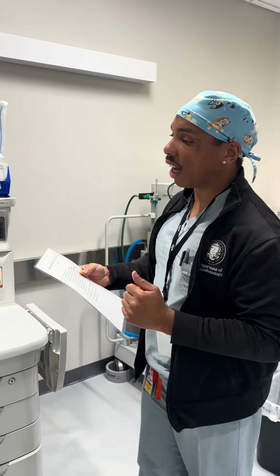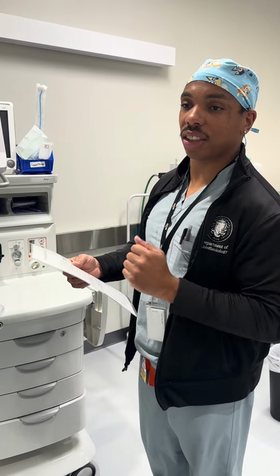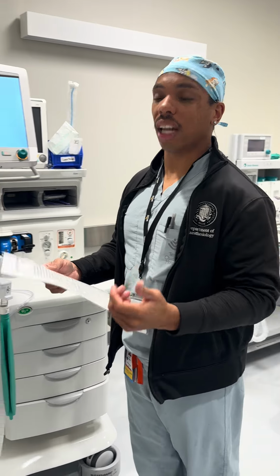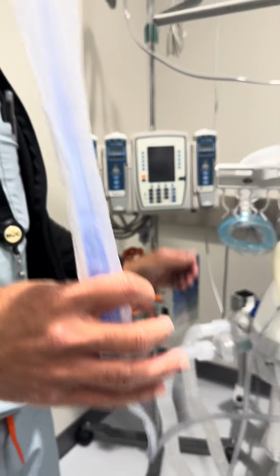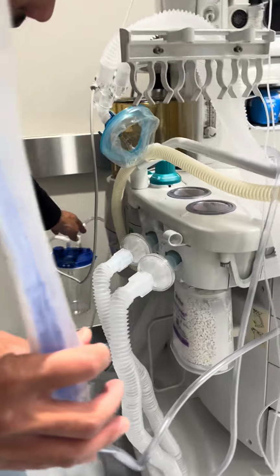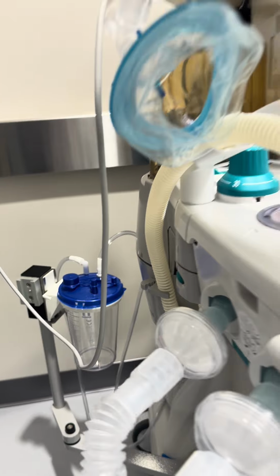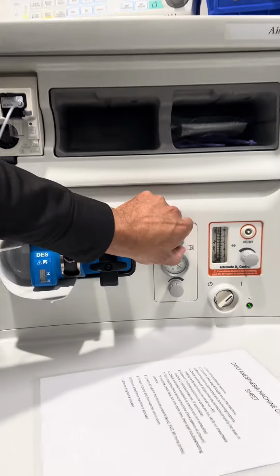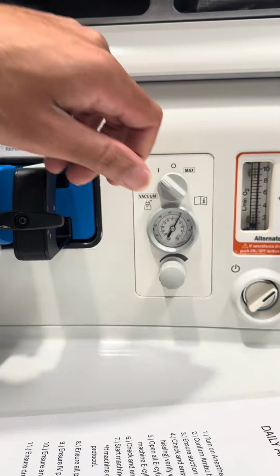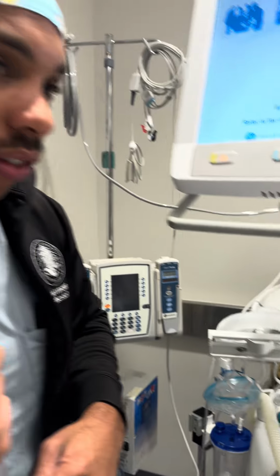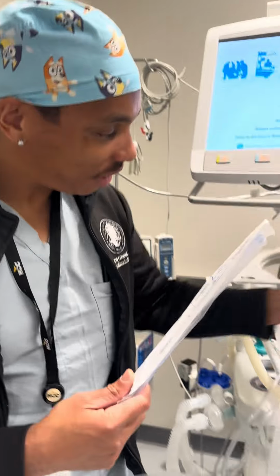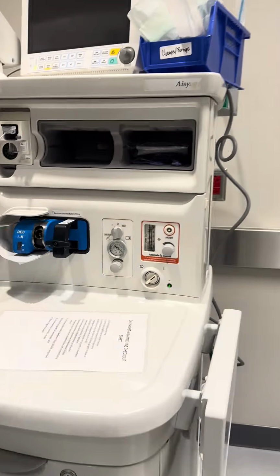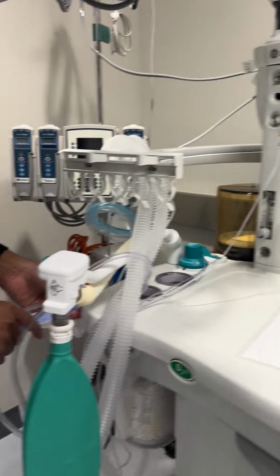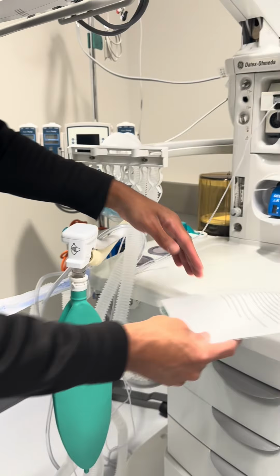So our next task will be ensuring that our suction is ready to go, which we talked about last week. So we're gonna come over, just make sure everything's all connected into our suction can. It's on patient, and then the vacuum is into the back of the machine. And then we wanna make sure that we turn it on and can actually hear the suction. So we know that we're good.